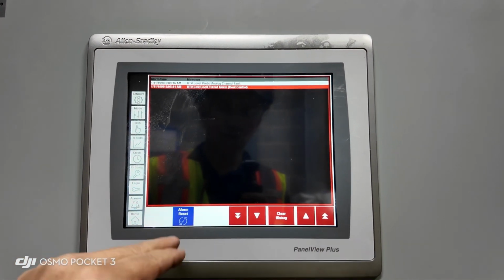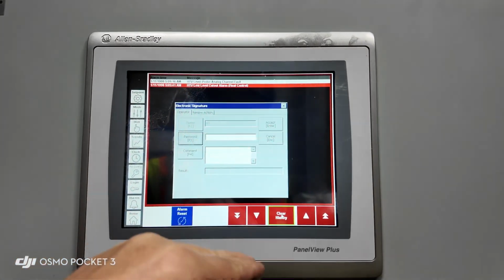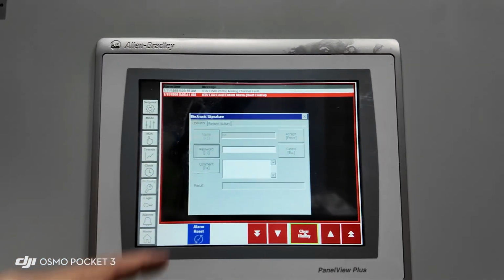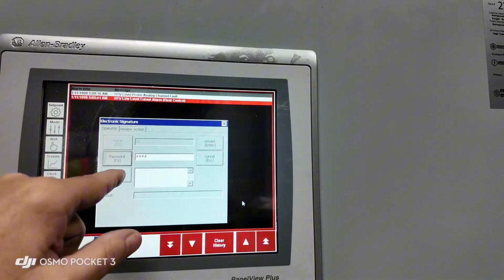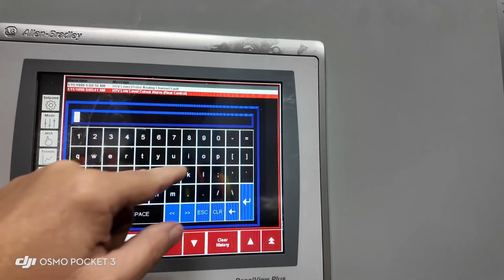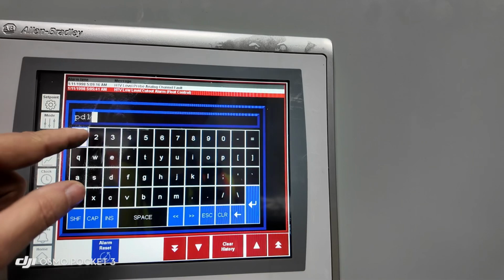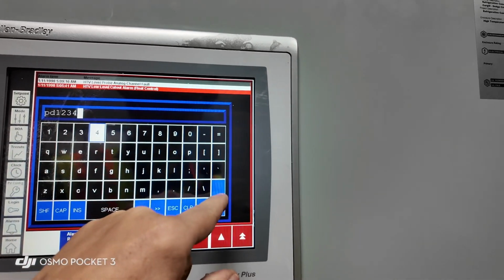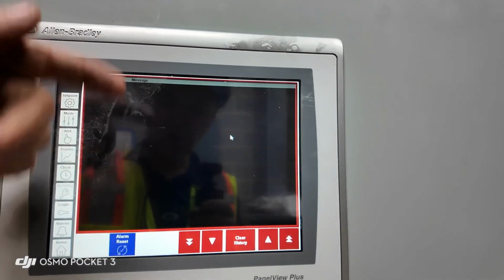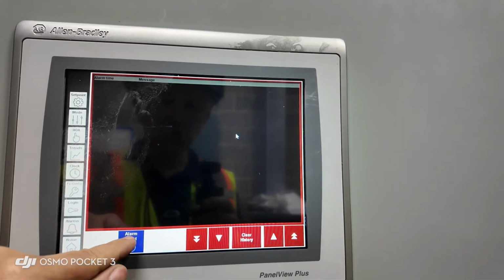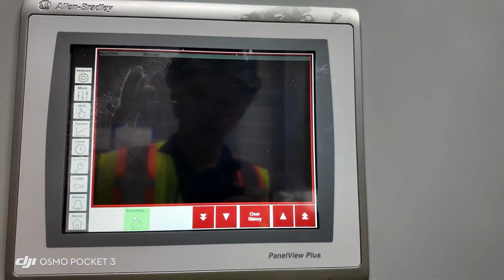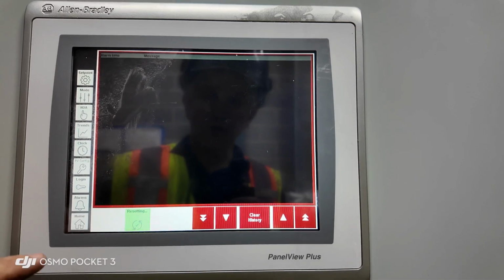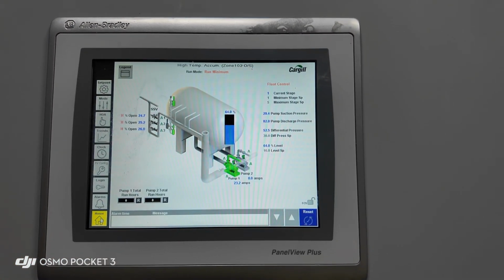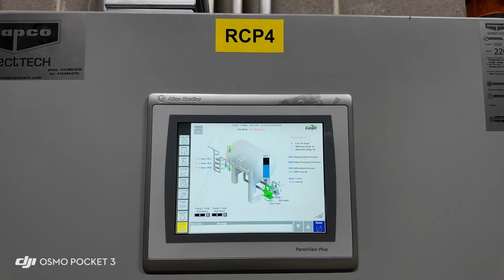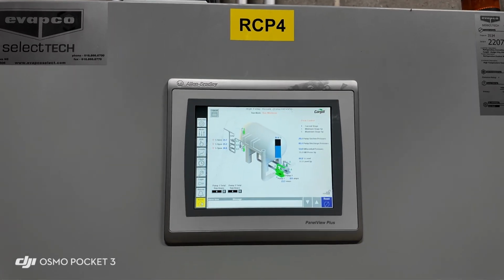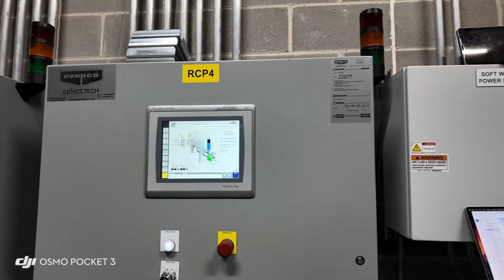This is where we would see alarm history. If we wanted to clear the history, we would go in here and enter our login, and we have to enter a comment in, and the comment has to be at least 6 characters long. I'm just entering one in. We accept that, and that will eliminate any alarm history. We also have an alarm reset button here. Okay? We then can navigate back to the home screen. That is all the screens on this panel view. Now I'm going to show you the inside of the panel.